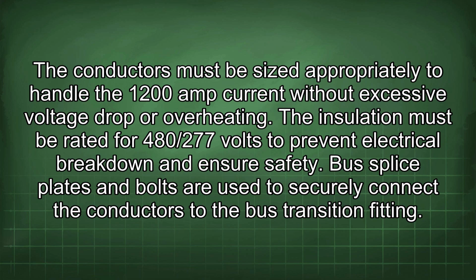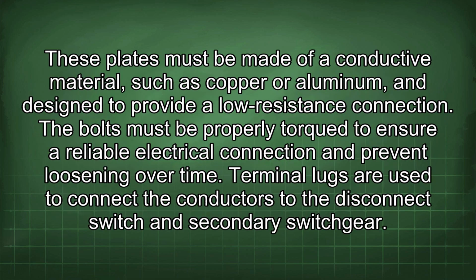Bus splice plates and bolts are used to securely connect the conductors to the bus transition fitting. These plates must be made of a conductive material, such as copper or aluminum, and designed to provide a low-resistance connection. The bolts must be properly torqued to ensure a reliable electrical connection and prevent loosening over time.